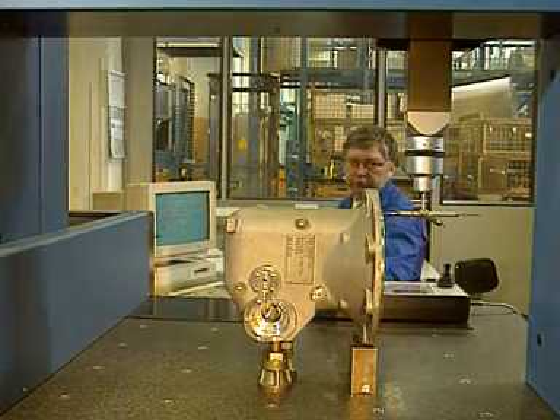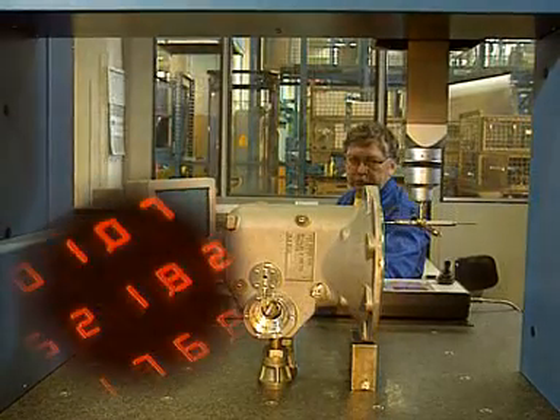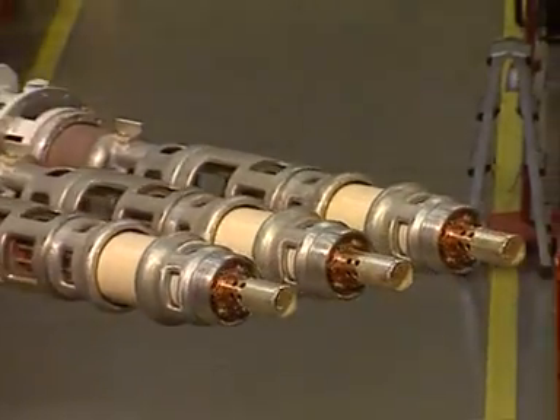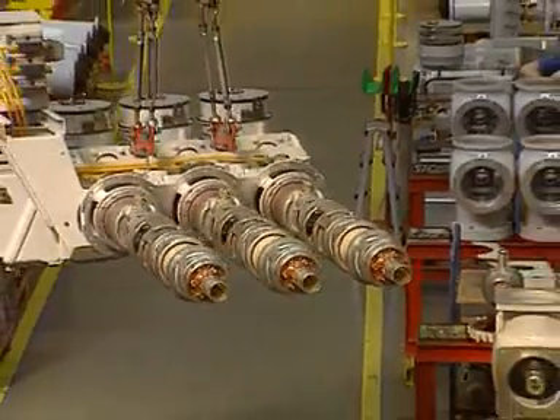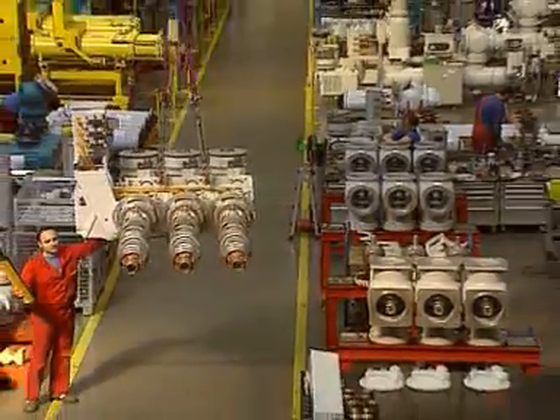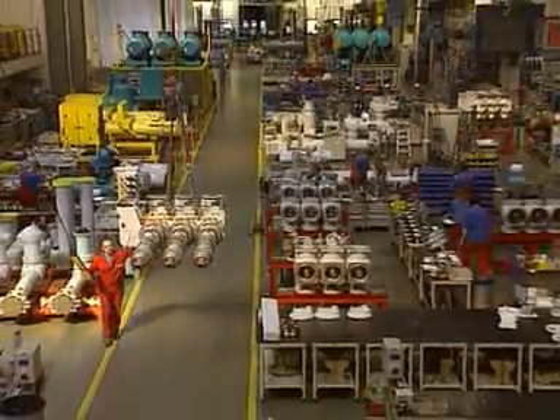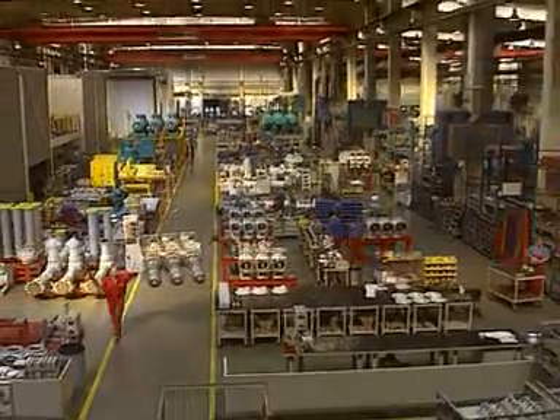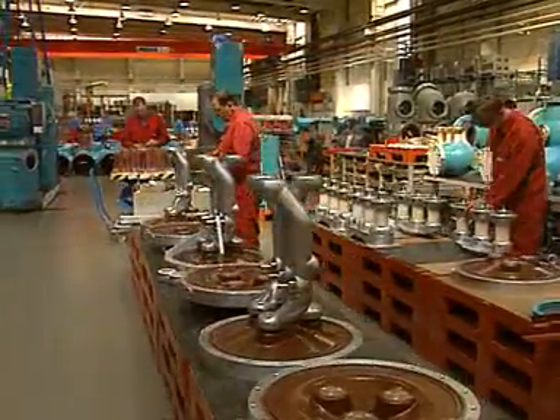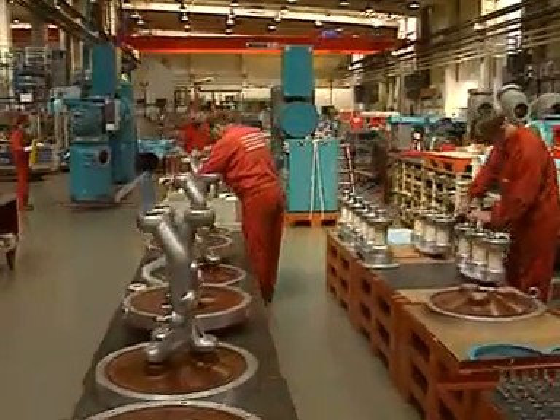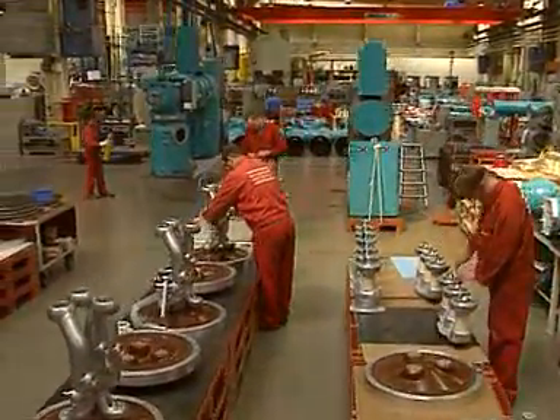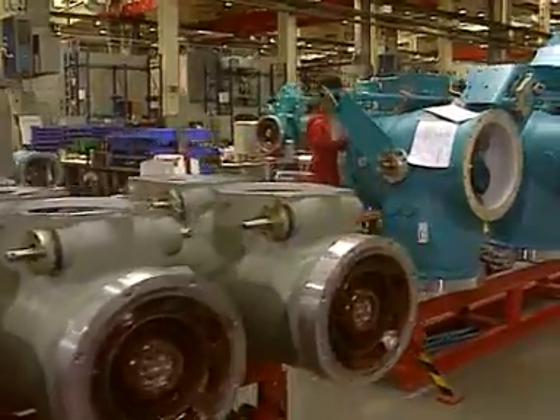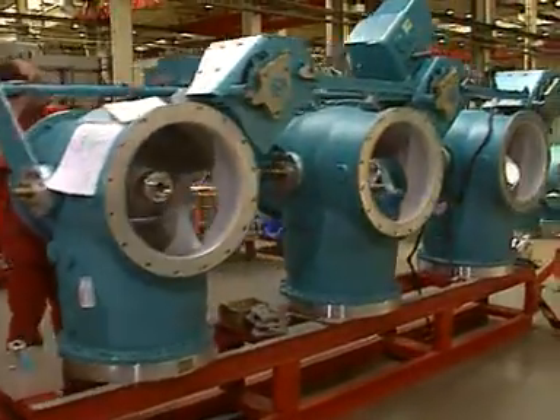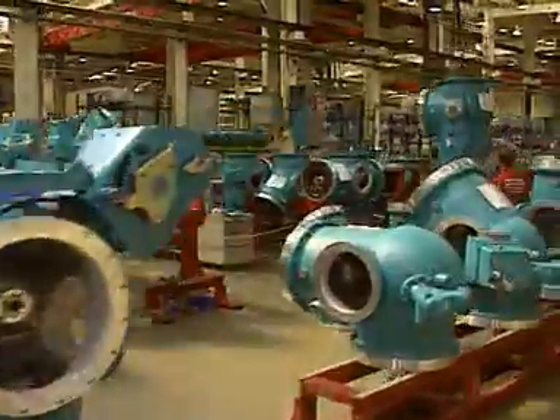Every important production step is followed by tests and inspections. Precision measuring equipment confirms adherence to the narrowest of tolerances. Components are assembled to make modules, and modules are assembled to form complete shipping units under clean room conditions. Hermetic sealing of shipping units before they leave the assembly halls makes sure that all GIS interiors stay clean in the long run.